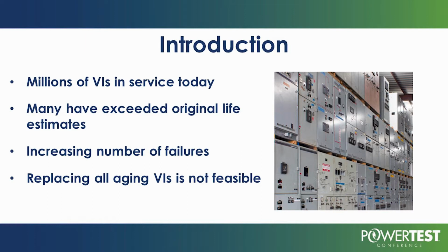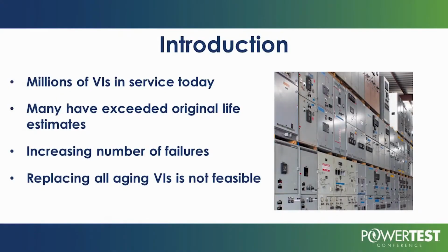We start to see real failure rates accelerate at about 30 years. Some of the cheaper made interrupters that are made offshore, we see even failure rates faster than that. Some of the interrupters we see seem to still be in reasonable condition after 30 years. It has to do with the manufacturing process, the materials, how well they built the materials and prepared them not to outgas. We've seen an increased number of failures.